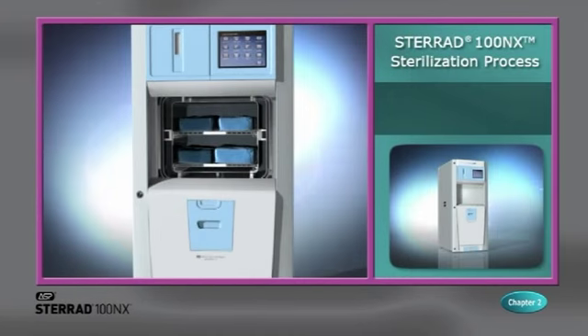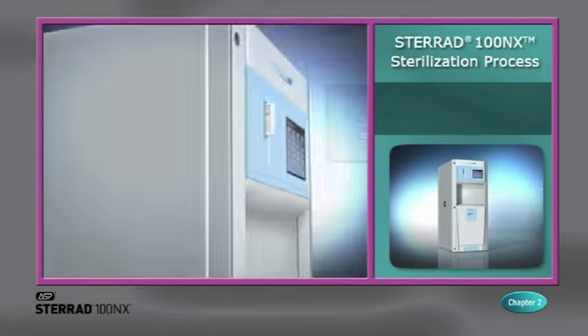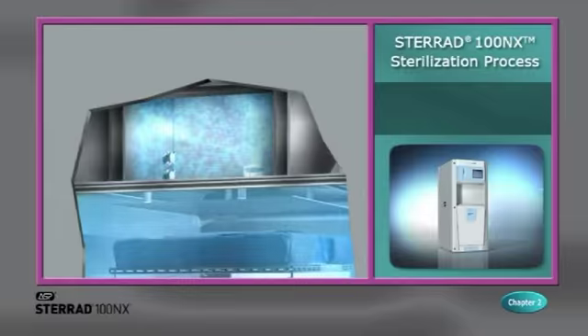The Sterrad 100NX sterilizer sterilizes medical devices via a sophisticated process. The key components of the process are: a vacuum is created inside the sterilization chamber where hydrogen peroxide sterilant is injected, surrounding the devices that need to be sterilized. This is the phase of the process in which microorganisms are killed. Next, a strong electrical field is applied, which creates plasma. The plasma breaks down the peroxide into a cloud of highly energized species. This produces a visible glow inside of the chamber and efficiently eliminates traces of residual hydrogen peroxide.